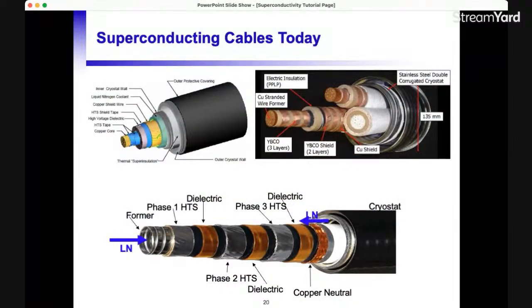Whenever you see utility substations with all the wires and transformers, that's why those are so big: the insulation for high voltage, hundreds of kilovolts, requires air, and you can't compact them together. If you go back to the slide, Pam, you'll see in the upper left-hand image that there are layers of insulation. Any underground cable has to have enough insulation to handle the voltage difference from ground to the high voltage conductor. In a superconductor cable, that's much less onerous than in a conventional cable.